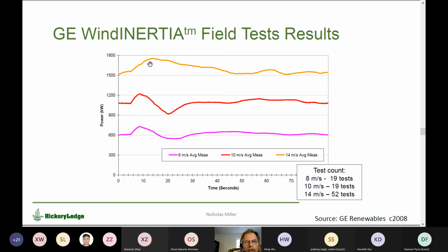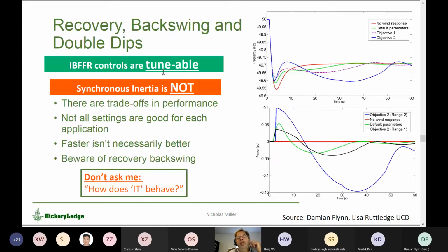And these cases show the turbines being overloaded by about 25% of rated. That's pretty generous. More modern ones are a little bit more limited than that. And you notice there's no backswing. So this is bimodal. There's two very different regimes of behavior.